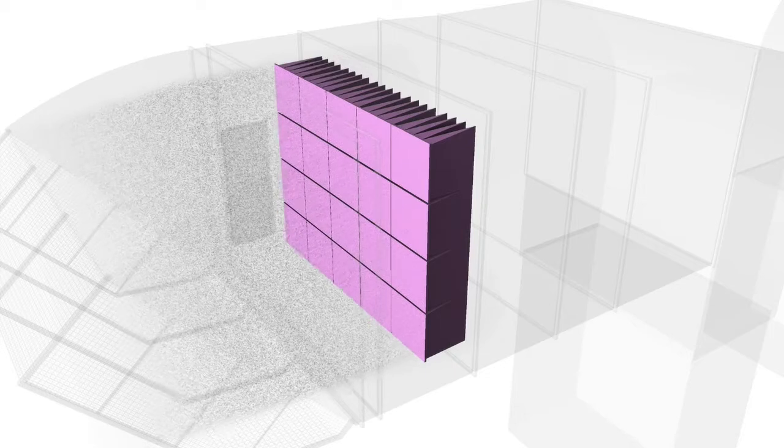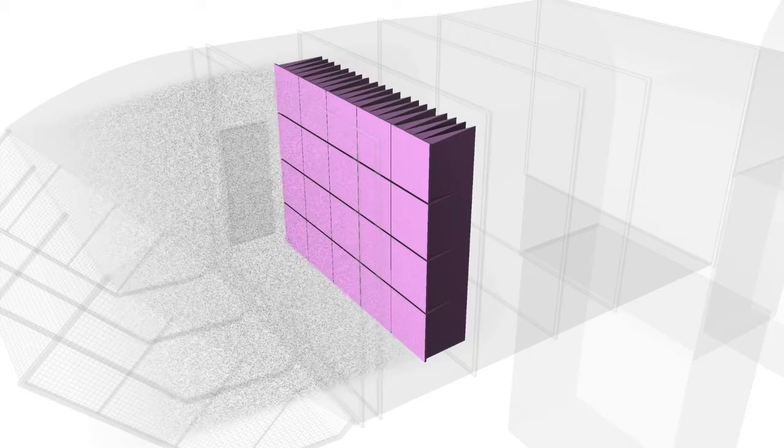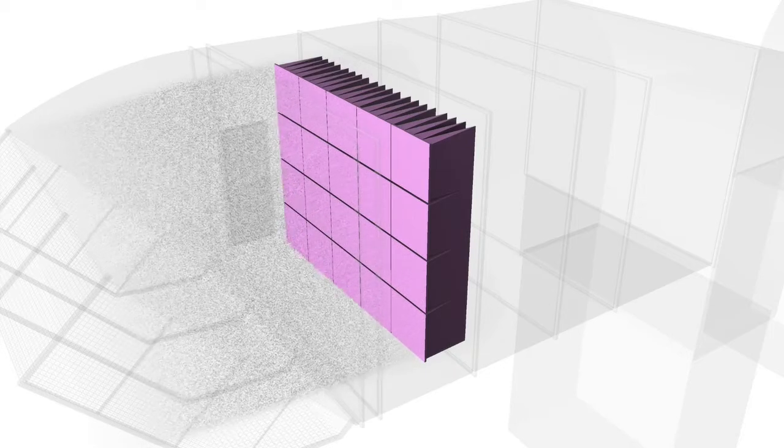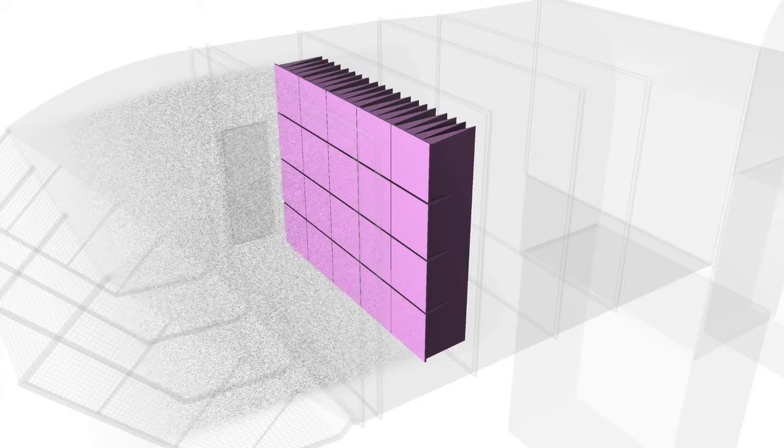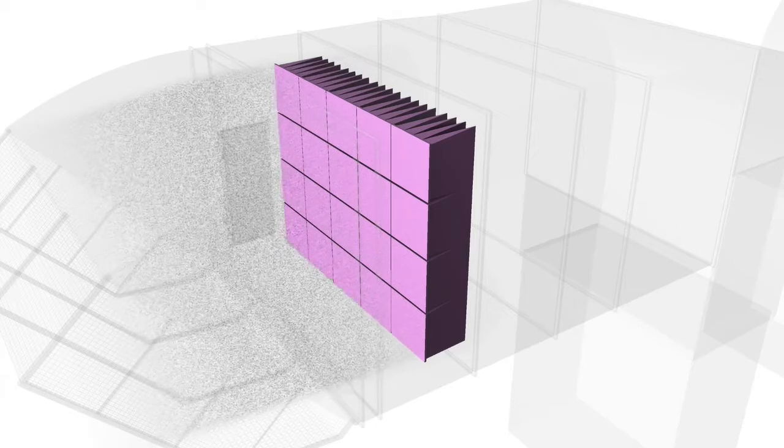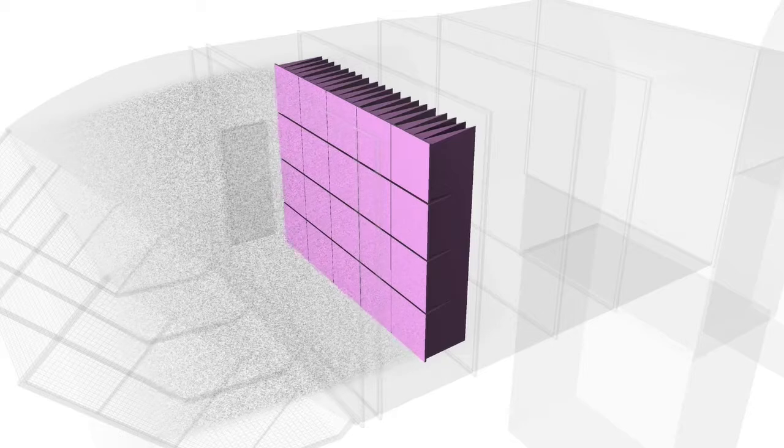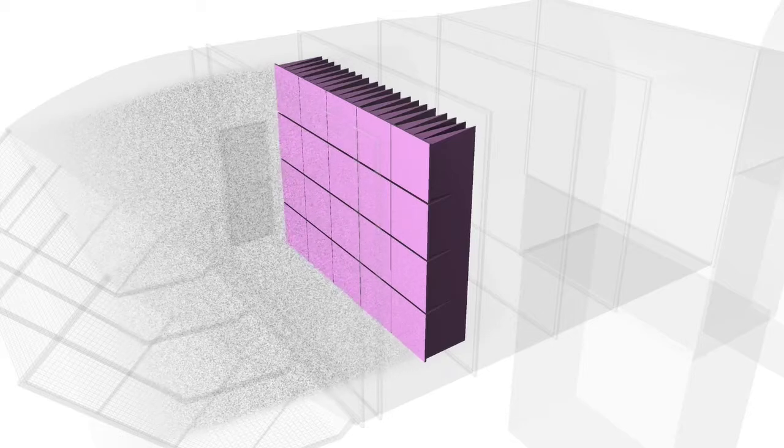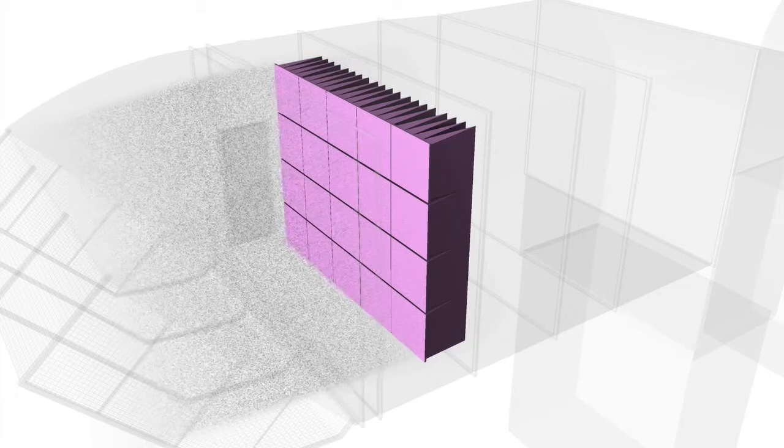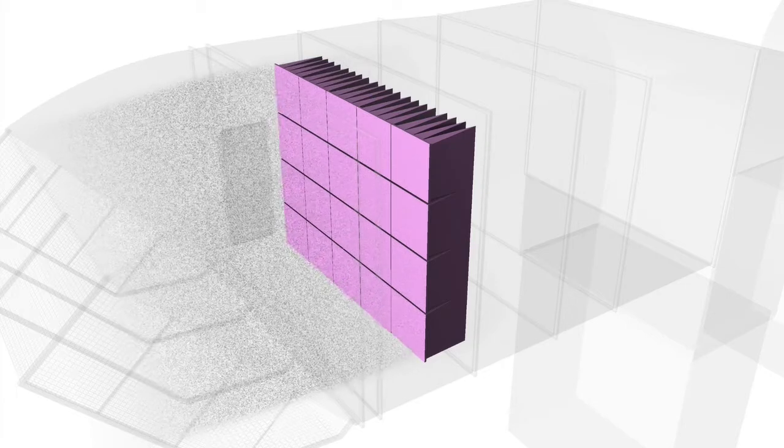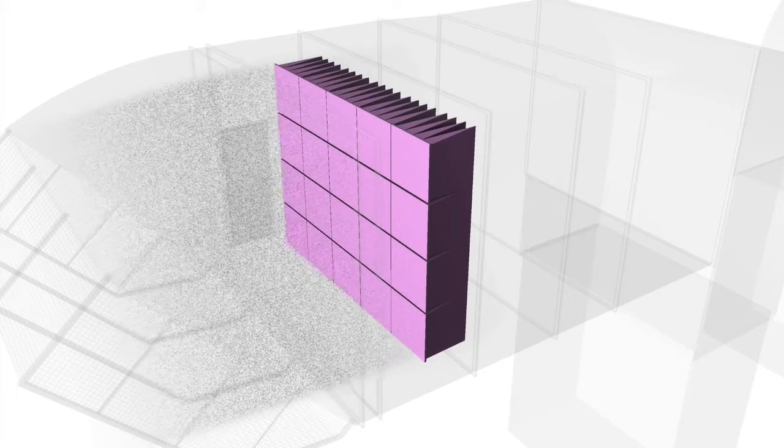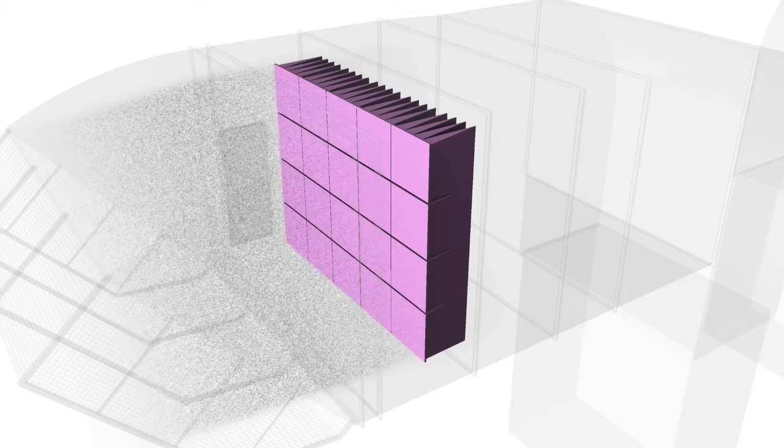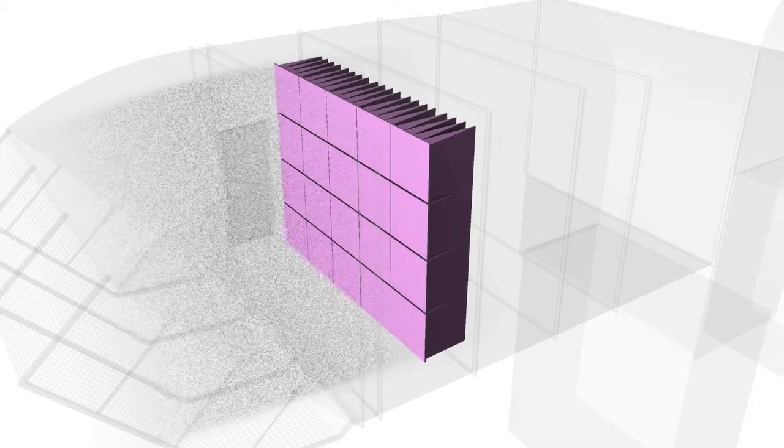Stage 3 is a coalescing high-efficiency filter. This stage captures fine dust and other solid particles such as dry salt and sand. Similar to stage 2, the high-efficiency filter also operates as a coalescer and allows captured salt aerosols to drain or re-entrain for final capture and removal by stage 4 of the system, preventing compressor fouling and blade erosion.